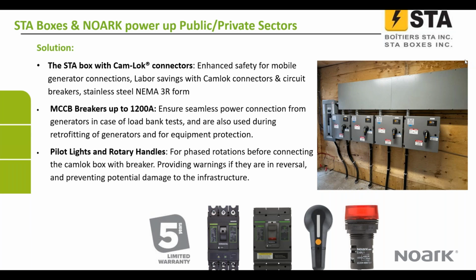We also use the pilot lights from NOARK for our phase rotation detector. This option allows you to verify the building phase rotation before powering up. It helps prevent reverse pump rotation and potential equipment damage.